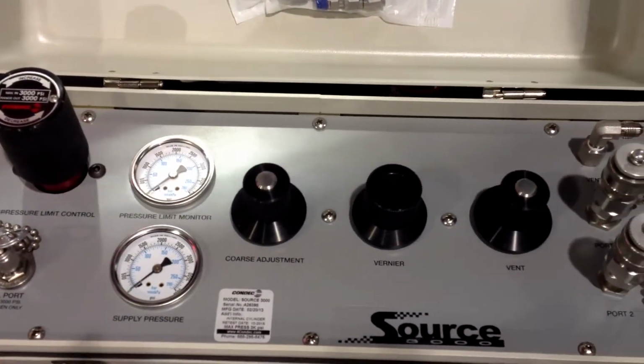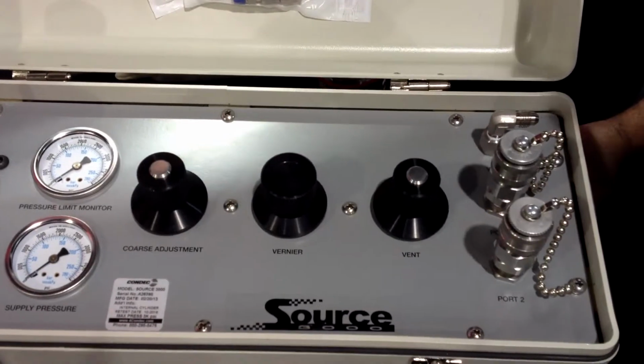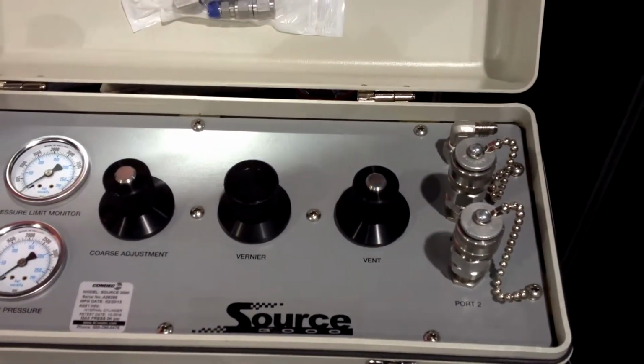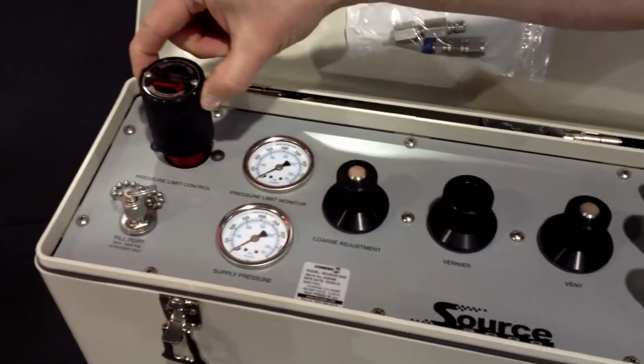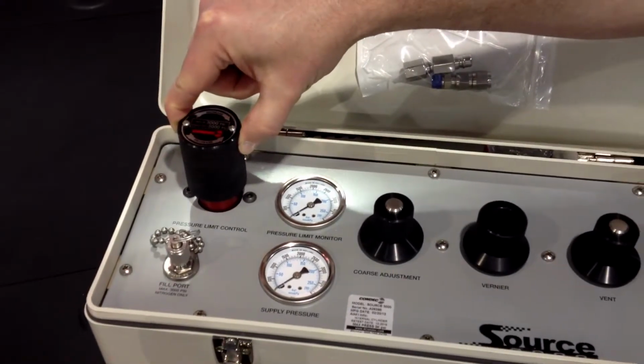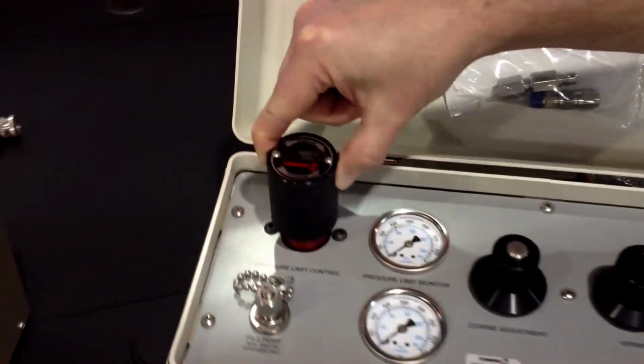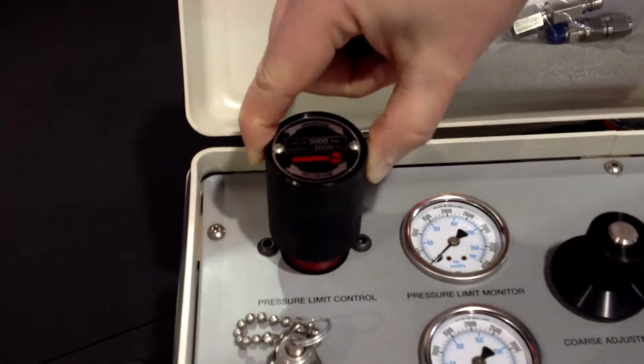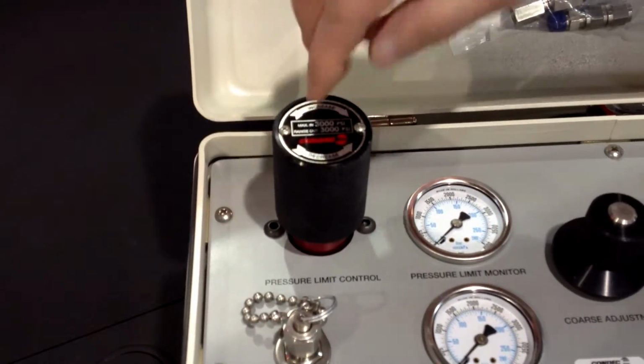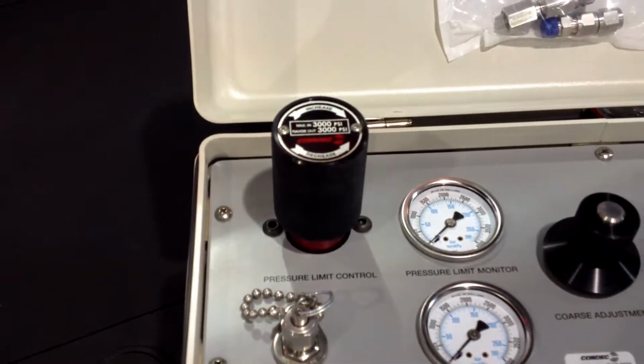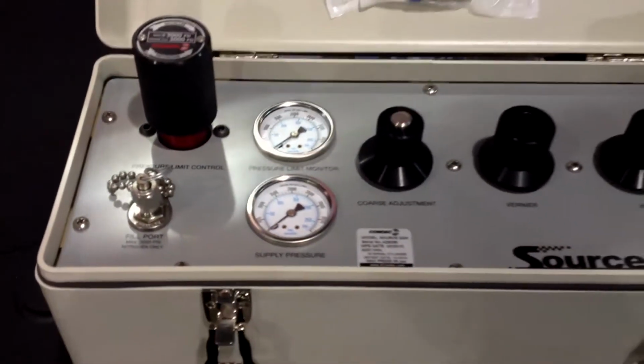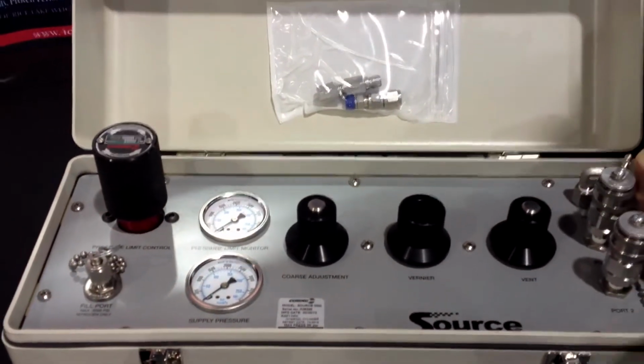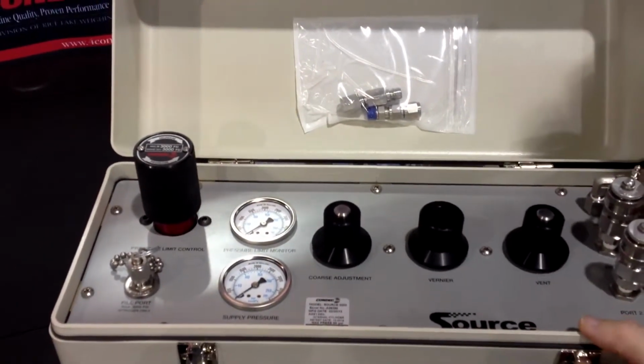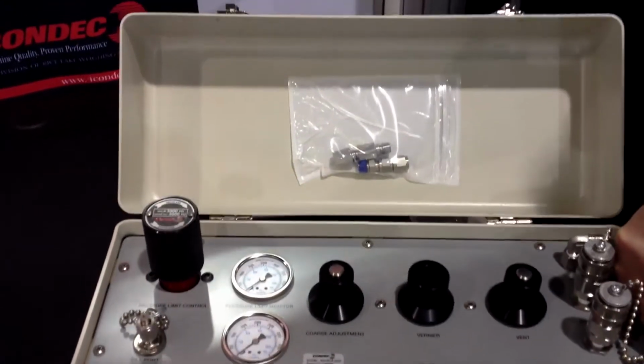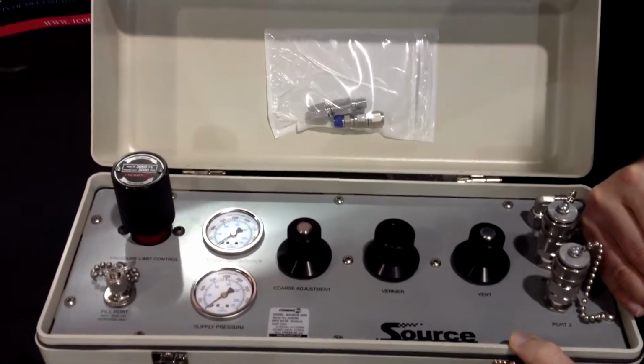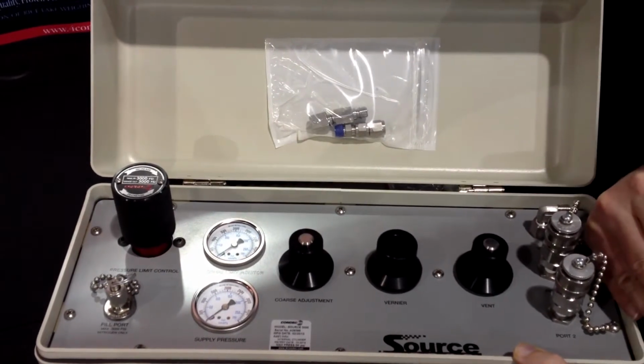The way it operates with the nitrogen cylinder inside is we have a regulator. Again, this is a Condec Reg 3000, and you can also purchase it separately. What that does is regulate your output pressure to your device under test so that it's protected from overpressuring. There's also an internal pressure burst disc to also protect from any errors occurring.